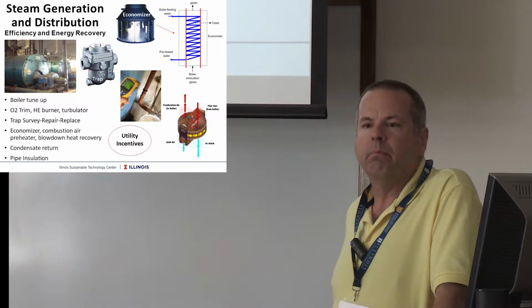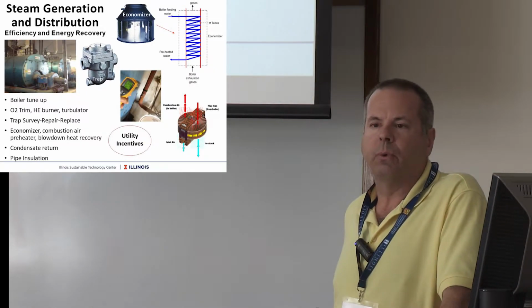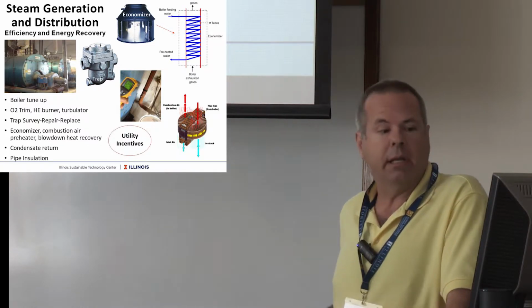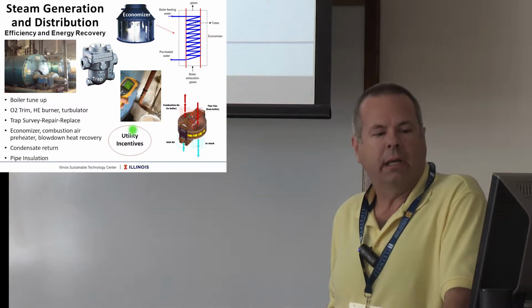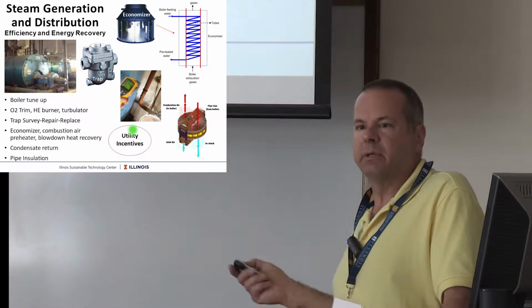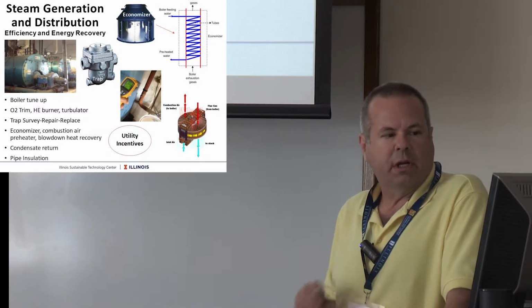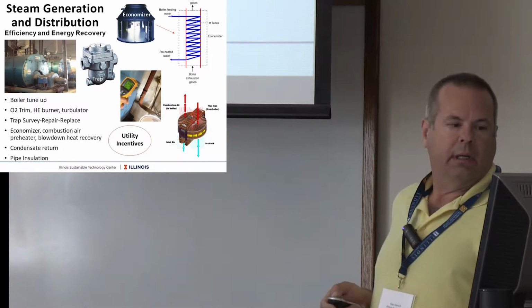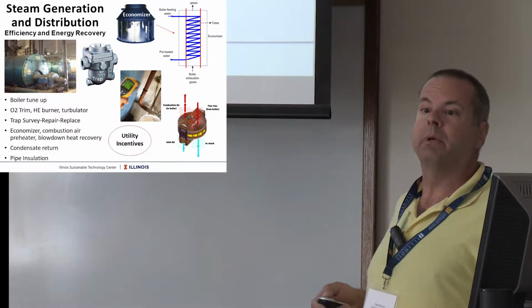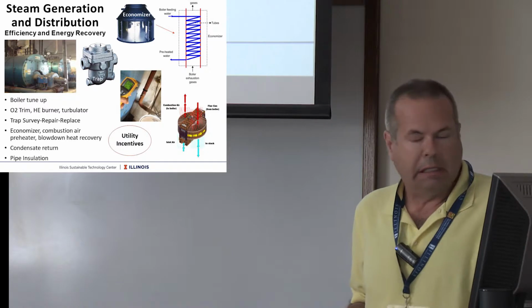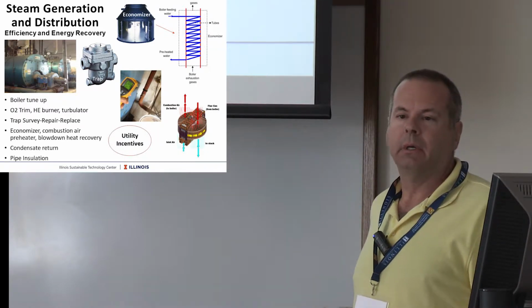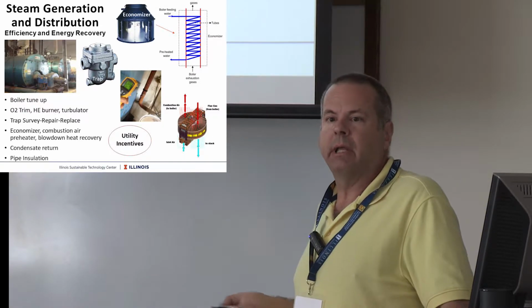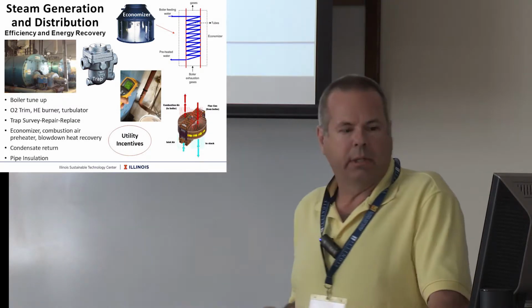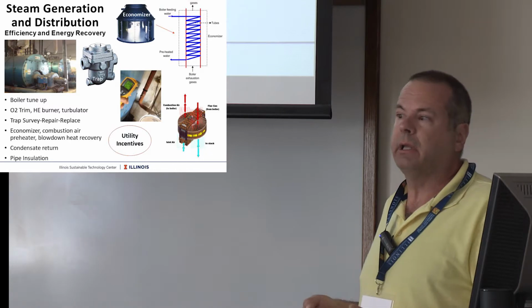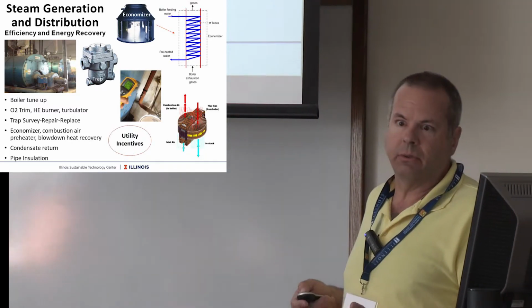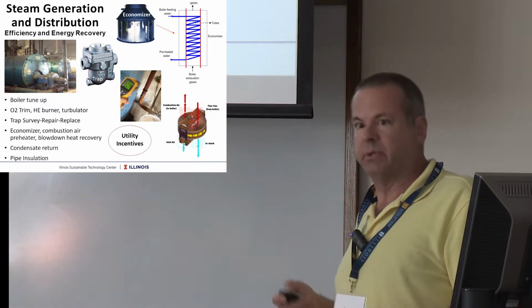Looking at process heating, boilers are a huge opportunity for waste energy recovery and just efficiency in general. And Ameren and ComEd and NICOR all have incentives for various aspects of efficiency when it comes to boilers. Just to throw out a couple of things here on the slide: boiler tune-ups, oxygen trim, combustion air preheating, high efficiency burners, an economizer that would preheat your incoming water with exhaust fumes, taking energy off the stack and bringing it into your process. Even combustion air preheating, the air coming into combustion. If you can raise your combustion air 80 degrees, you can increase efficiency roughly 1%, which is significant for boilers.